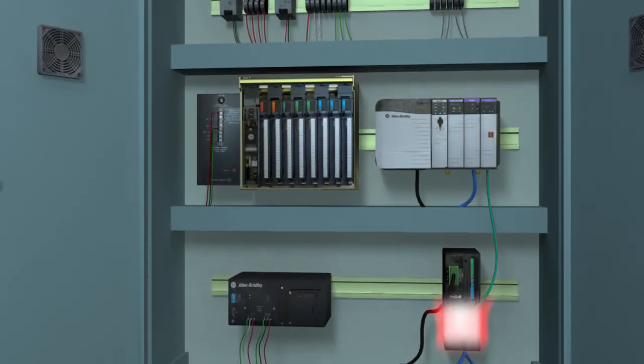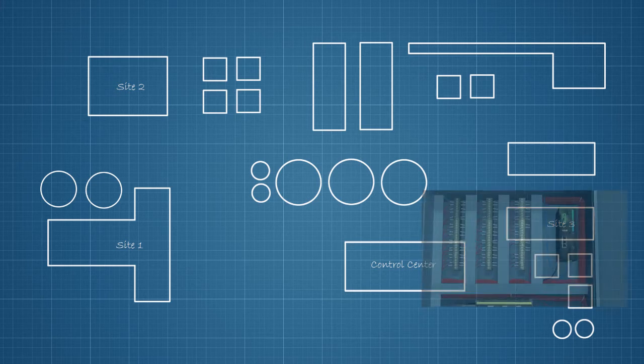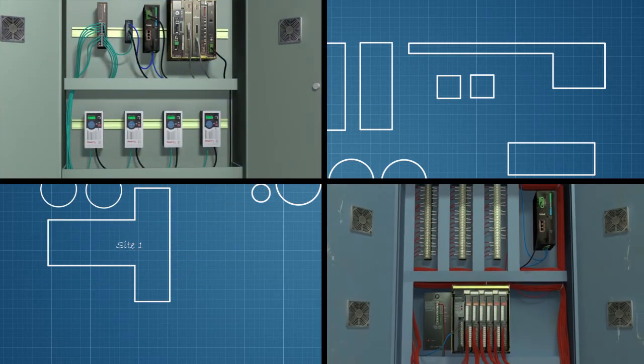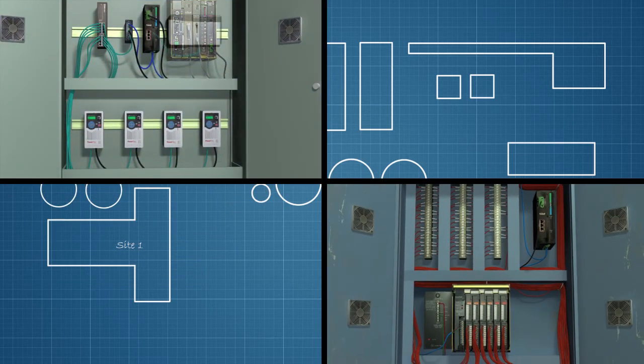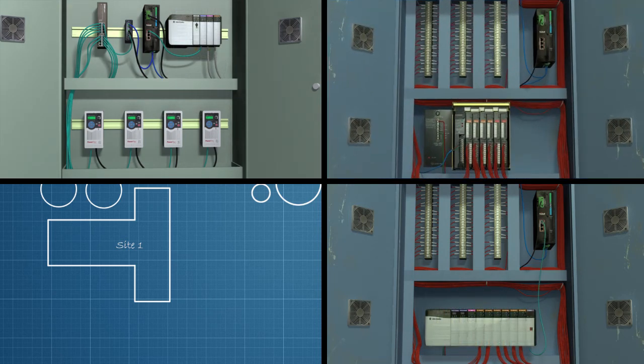If there are problems with the program, you can simply switch back to the old PLC5 and not skip a beat, reducing the risk of prolonged downtime. Once the new control system is running smoothly, you may begin upgrading your remote I.O. nodes to Ethernet IP devices one at a time as scheduled downtime permits. As each remote I.O. node is decommissioned, you end up with spares.